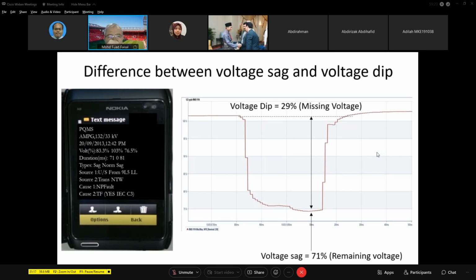You can see on the same slide the SMS. This is a Nokia handphone. This is my old handphone. I still kept my Nokia. So it shows voltage. Remember, you can see on the slide, the red phase is 83%, which is the voltage sag. It means this is the remaining voltage. The yellow phase is 103%, normal voltage, and then the blue phase, 76.5, is the remaining voltage sag. So this is the voltage that remained during the event. So we just take 100 minus this value, and we have the dip. So this is the difference between the definitions of voltage sag and dip. And voltage sag is used widely in America, IEEE, but voltage dip is used in Europe, IEC, etc.